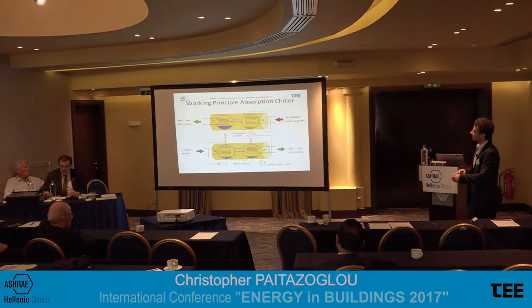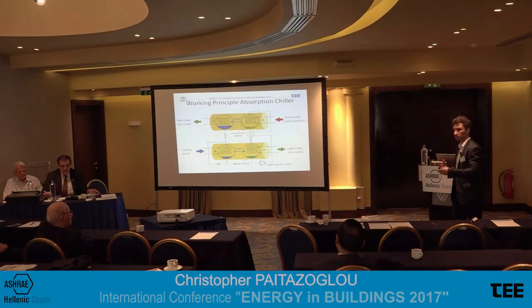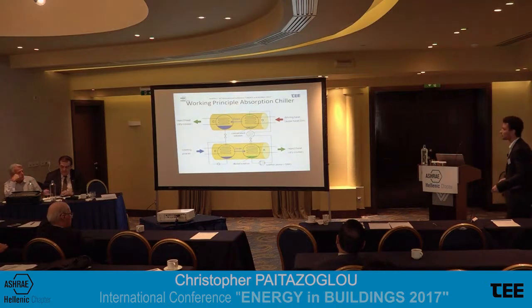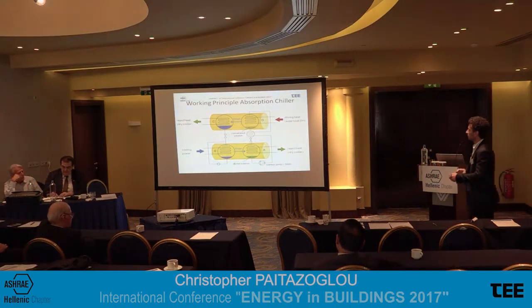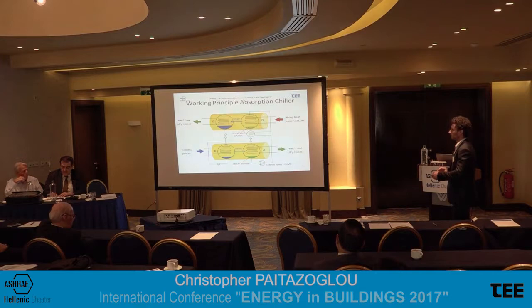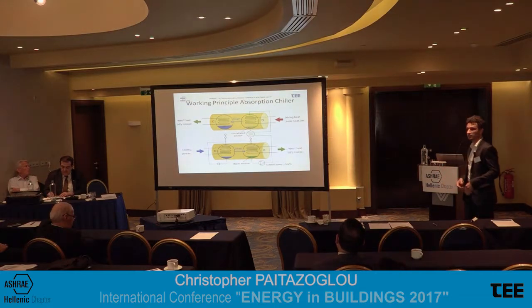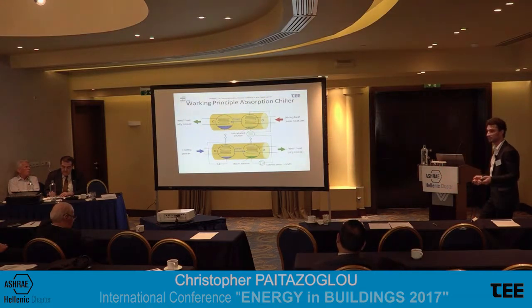And then we have steam going to the condenser, and in those processes, absorber and condenser, due to the dilution and to the condensation heat, we have abundant heat that has to be rejected. Whereas in the generator, we have to provide the chiller with a driving heat source. That can be a solar field, that can be a district heating system, and so on.